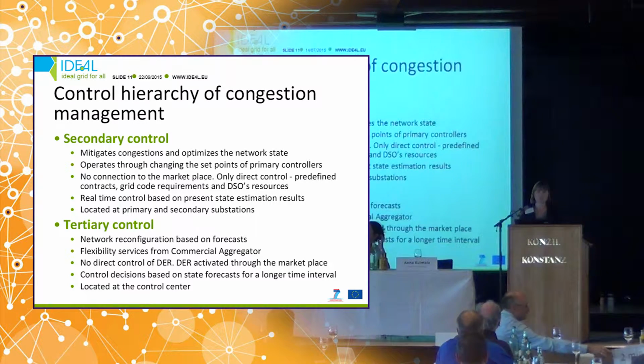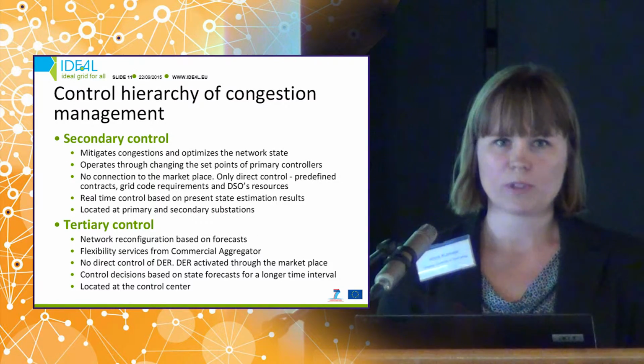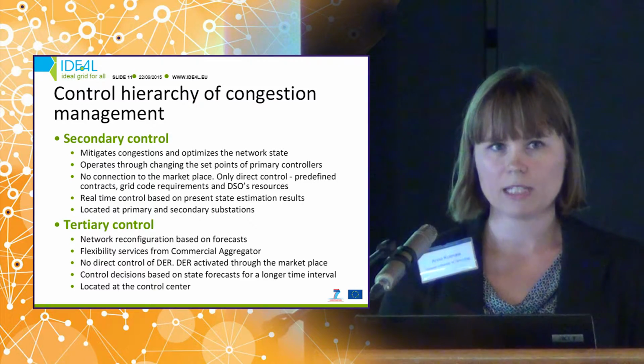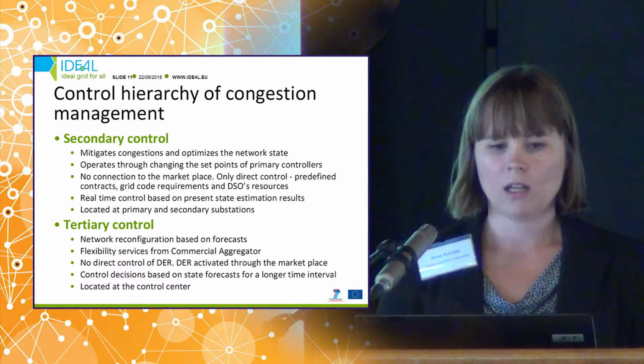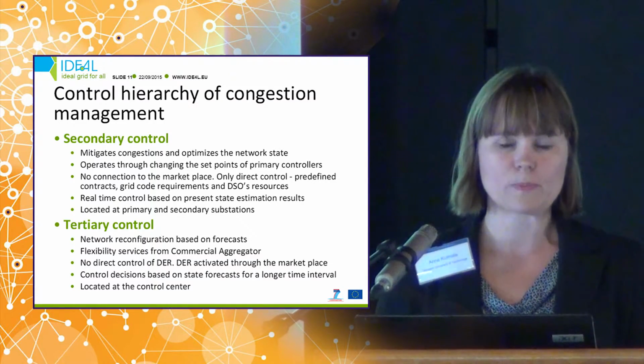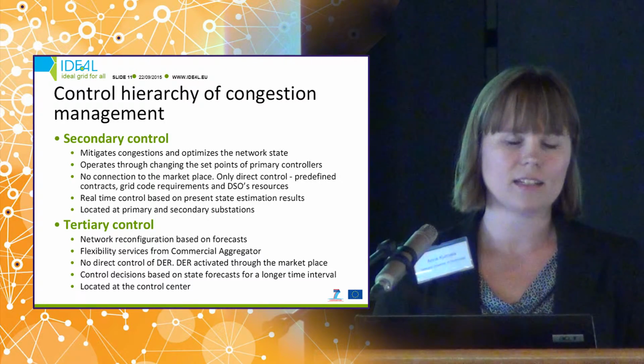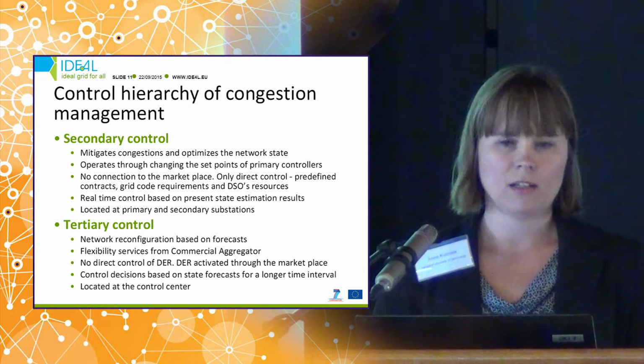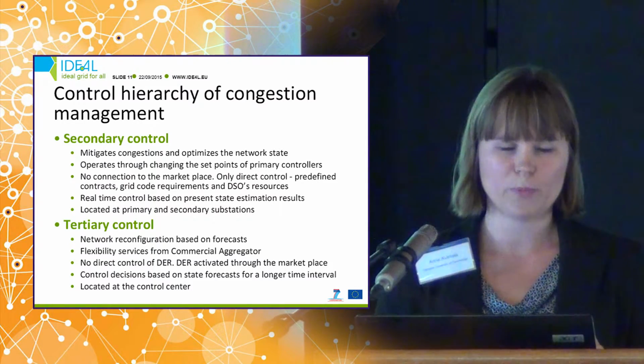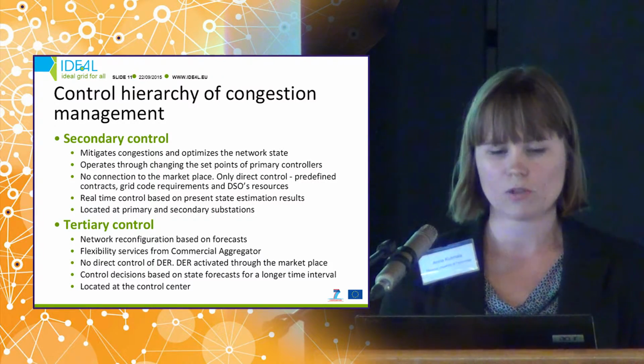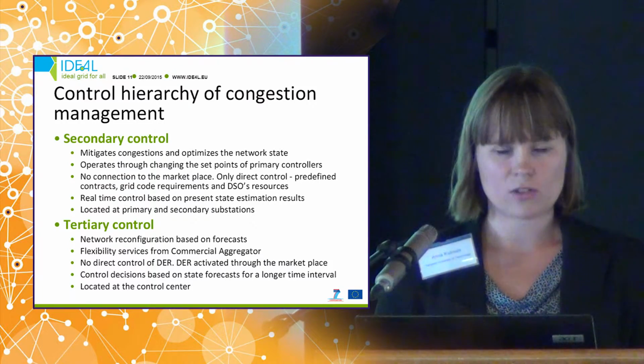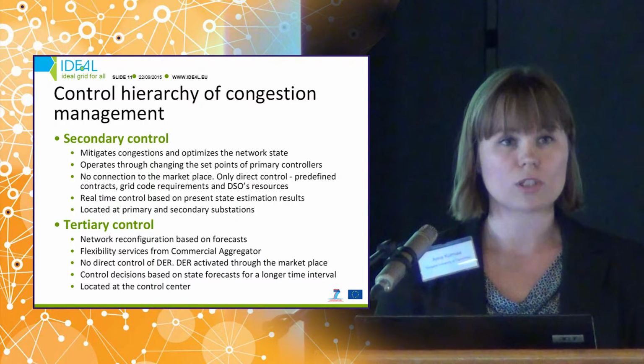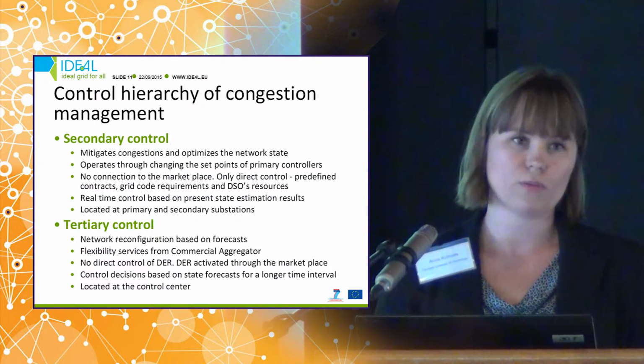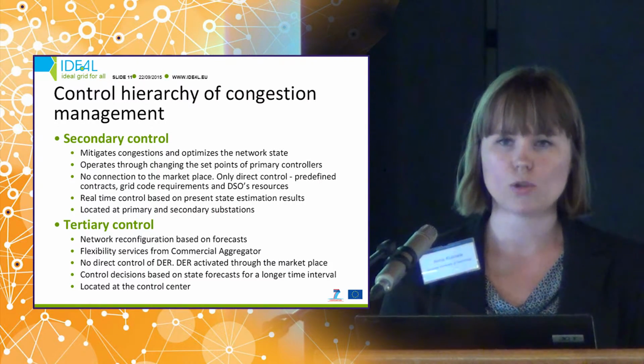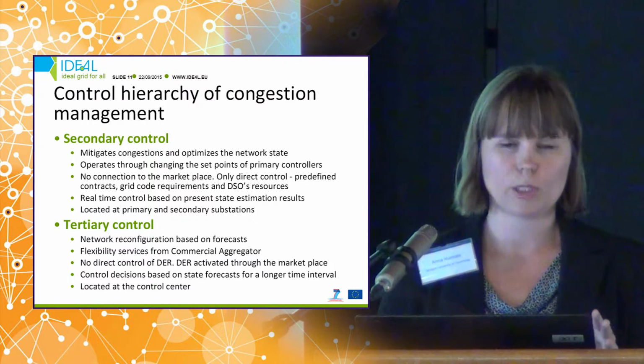We have divided the control into secondary and then tertiary parts. The secondary control is operating in real time, and its job is to make sure that the network is always at an acceptable state, and after that optimize the network state. It uses state estimation data to determine the control actions, and these secondary controllers are located at the primary and secondary substation automation units, and they control either the MV or the LV network, depending on where the control is located. It operates through changing the set points of primary controllers that can be, for instance, the automatic voltage control relays of the transformer OLTCs or the voltage controllers of DG units. And it has no connection to the marketplace, so it operates directly when it's needed.